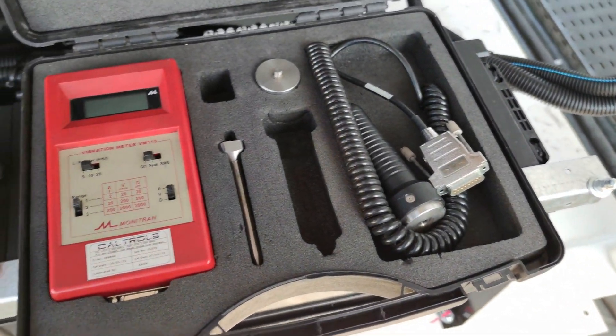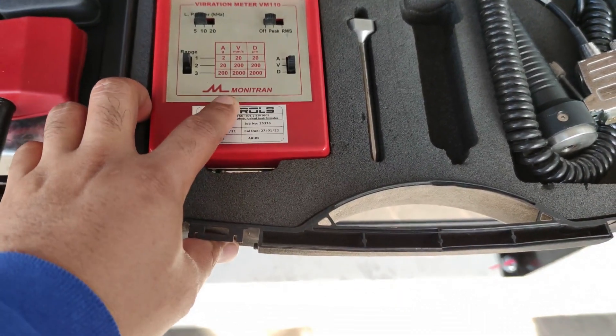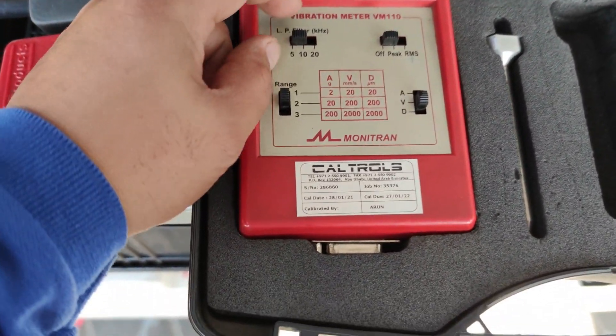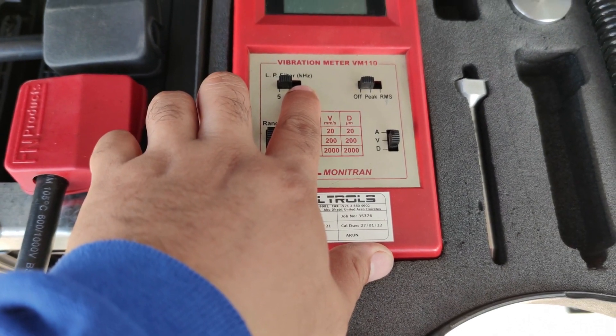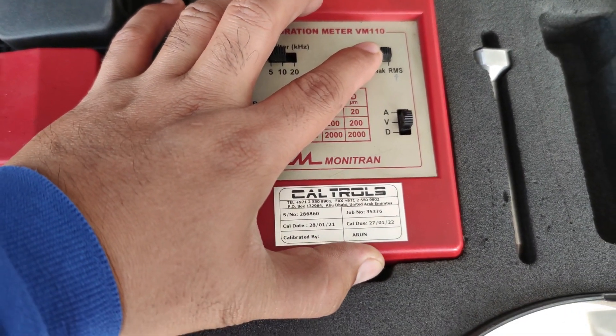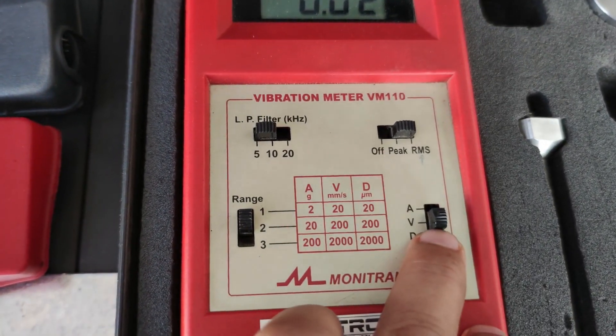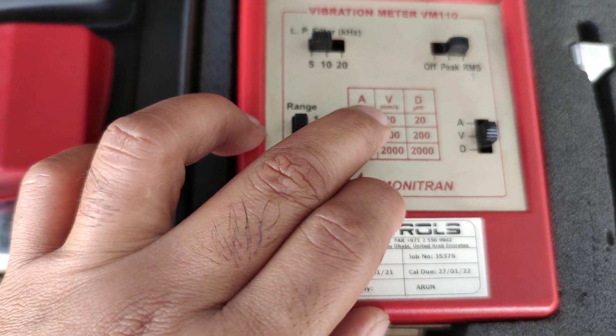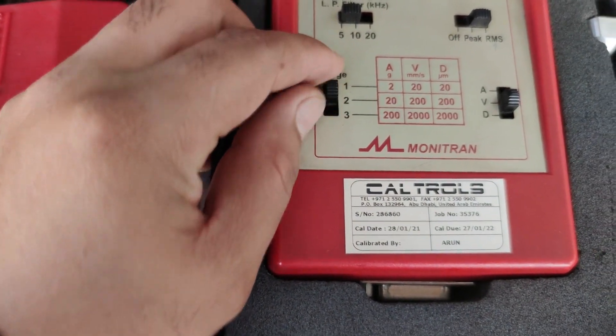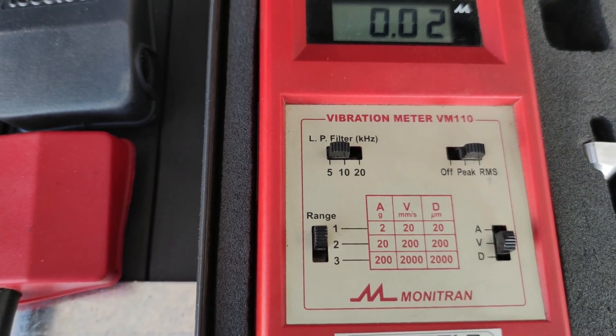Here is our vibration meter — this is the Monitran vibration meter. For the calibration, we're going to put it at five kilohertz and it should be at the set point of RMS. The unit is millimeter per second, so this is our set points for our testing.